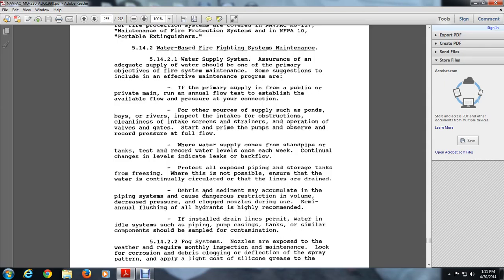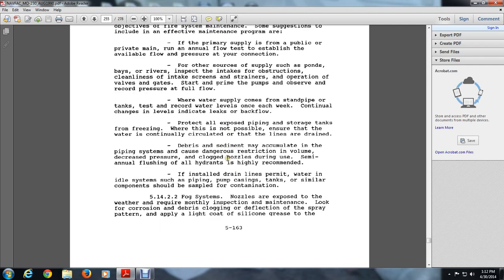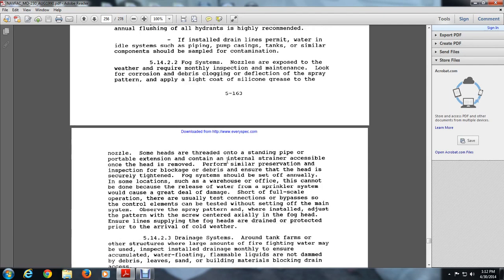5.14.2.2 Fog system. Fog system nozzles are exposed to the weather and require monthly inspection and maintenance to look for corrosion, debris, clogging, and deflection of the spray pattern, and apply a light coating of silicone grease to the nozzle. Some heads are threaded onto the pipe, with portable extensions containing internal straining accessibility. Once heads are removed, perform similar preservation, inspect for blockage and debris, and ensure the head is securely tightened. Fog systems should be tested annually.